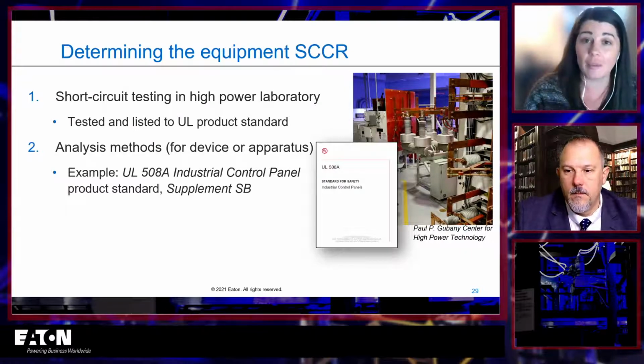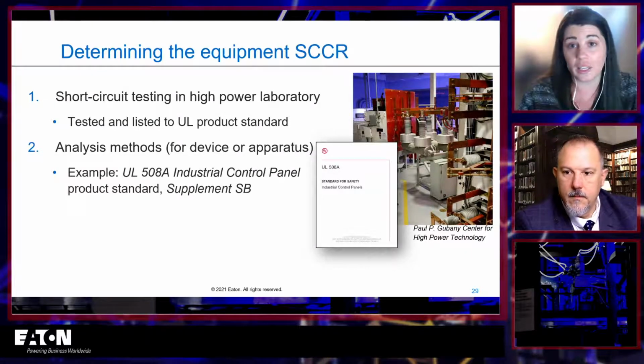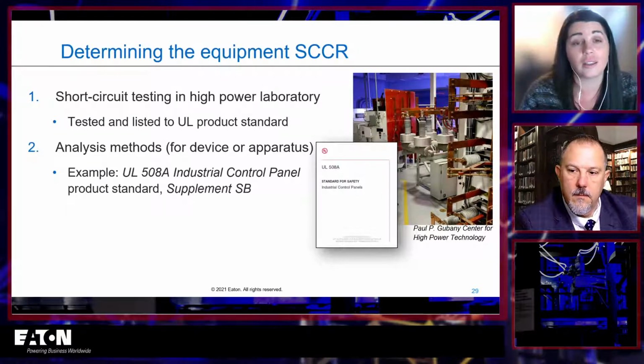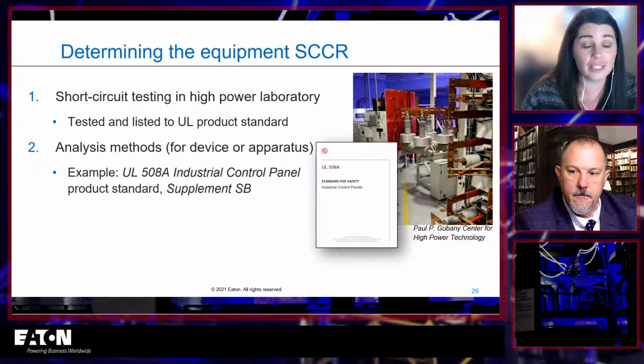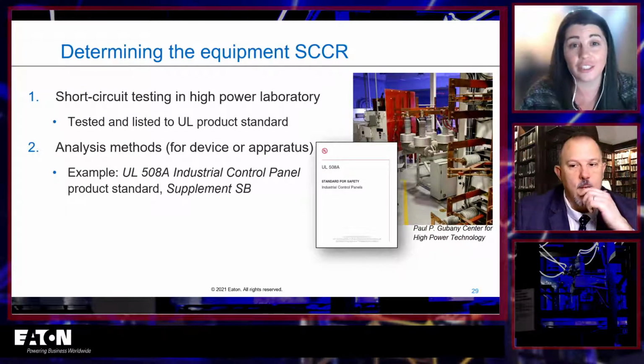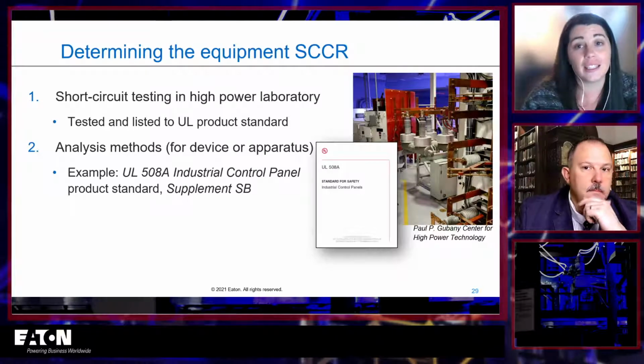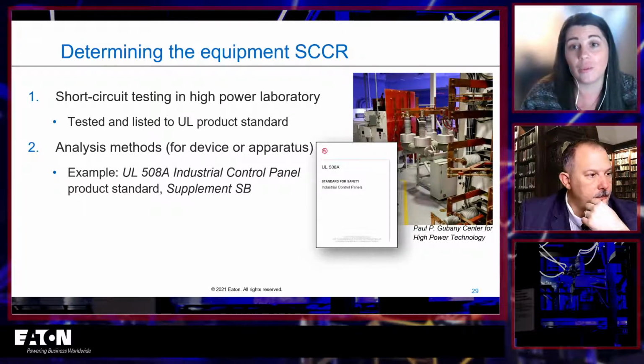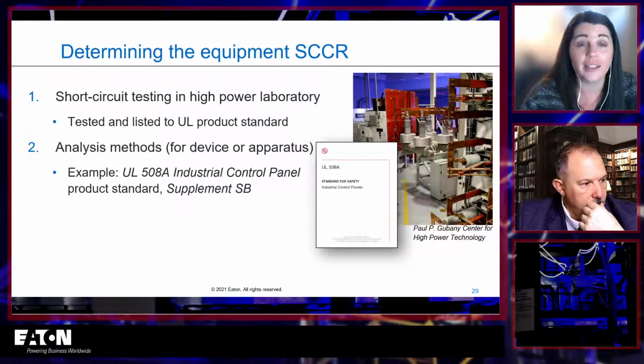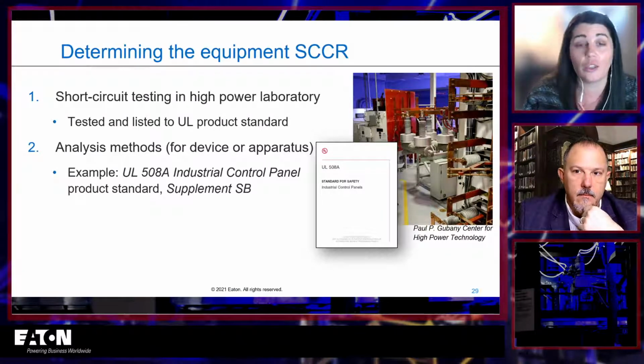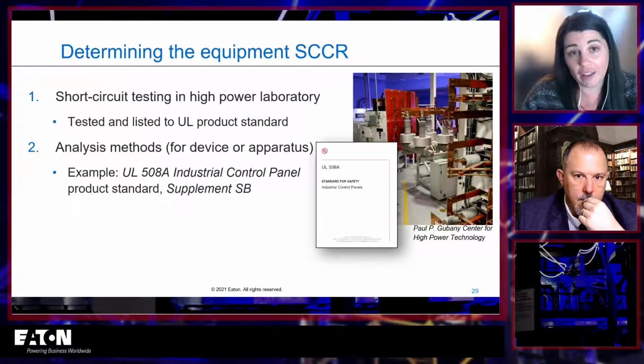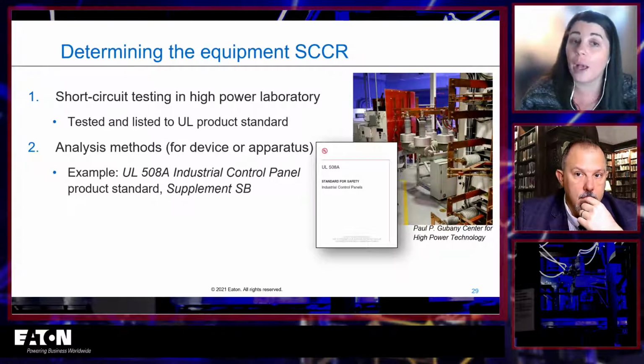And if you're building the same thing over and over again, this makes perfect sense, right? Because you just have to get it tested once, and you have a rating that you can use over and over and over again. For pieces of equipment that tend to be a little bit more custom, such as control panels, we have an analysis method. The one we're going to talk about is UL 508A, Supplement SB, which details a way that you can determine a short circuit current rating for an industrial control panel without having to do the short circuit testing, right? So you don't actually have to test it. You can figure it out based on what's inside.